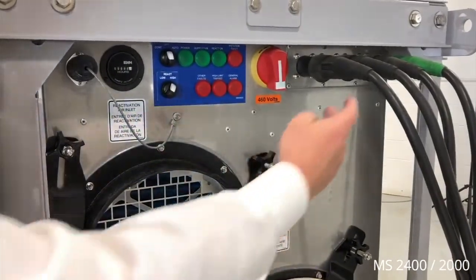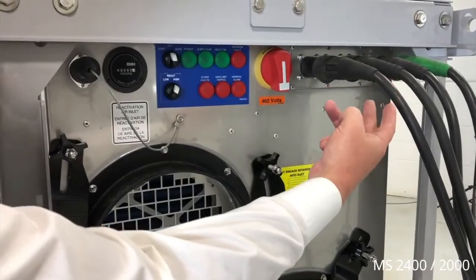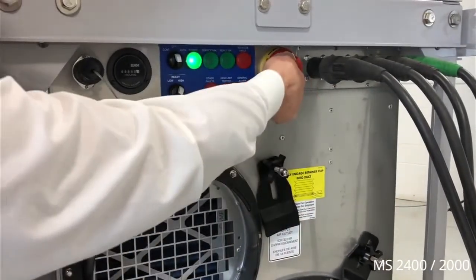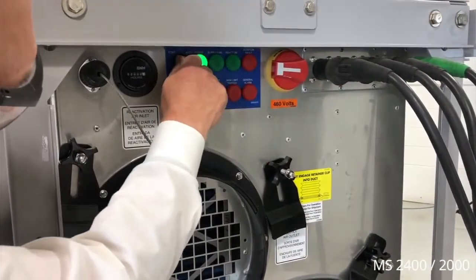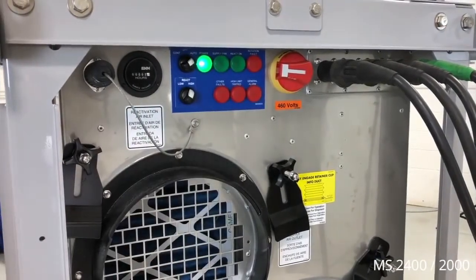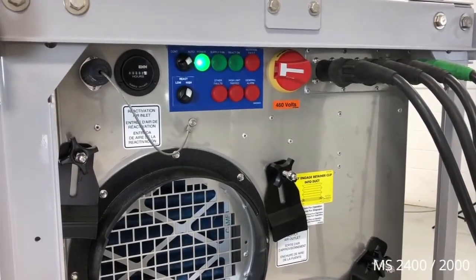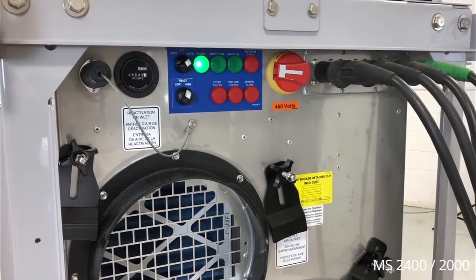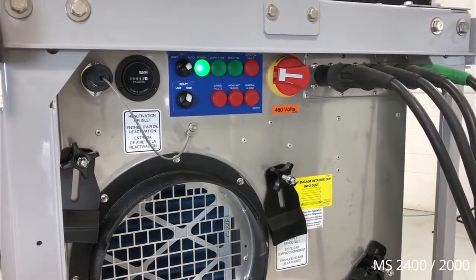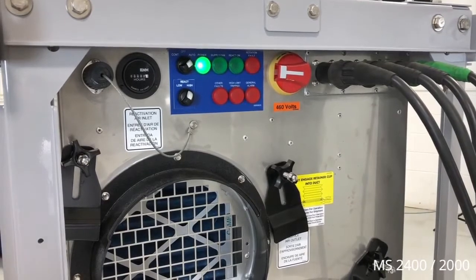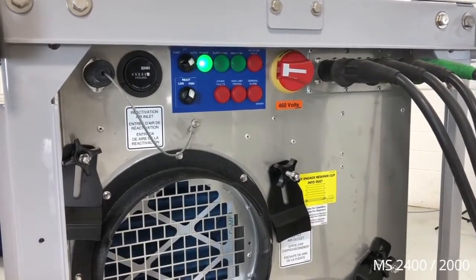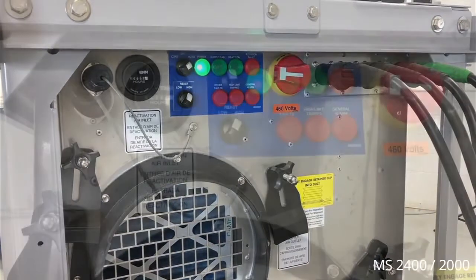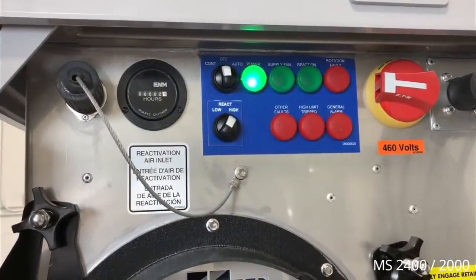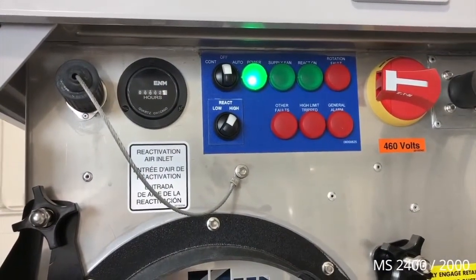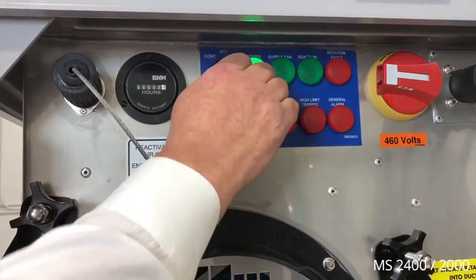Okay, now we have reversed 2 of the power leads coming into the unit. We can now go ahead and turn the power switch back to on and turn the unit back to auto. And again, we have the delay where the microprocessor is going through its self-check process. If the self-check is complete, the unit should start within about a minute of applying power to the circuit. With the phase now corrected, we can ask the unit to operate. We can turn the switch to the auto position.